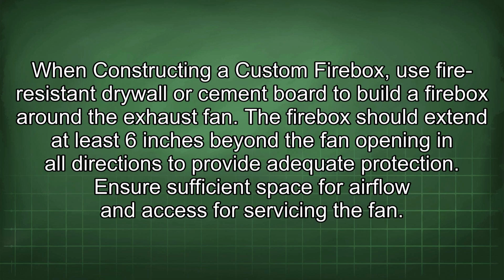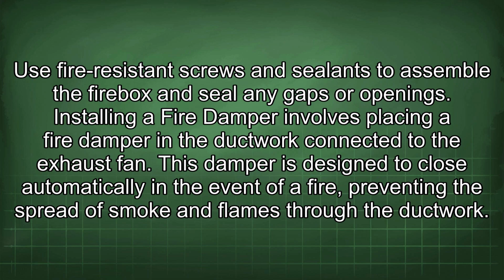When constructing a custom firebox, use fire-resistant drywall or cement board to build a firebox around the exhaust fan. The firebox should extend at least 6 inches beyond the fan opening in all directions to provide adequate protection. Ensure sufficient space for airflow and access for servicing the fan. Use fire-resistant screws and sealants to assemble the firebox and seal any gaps or openings.